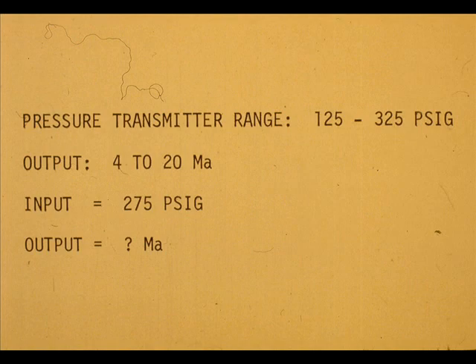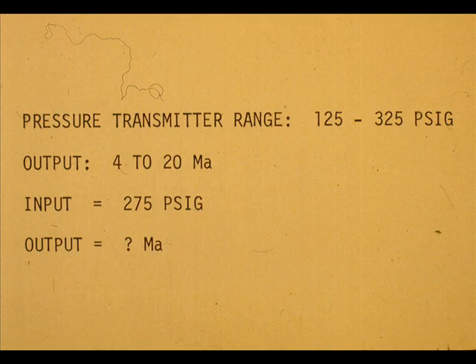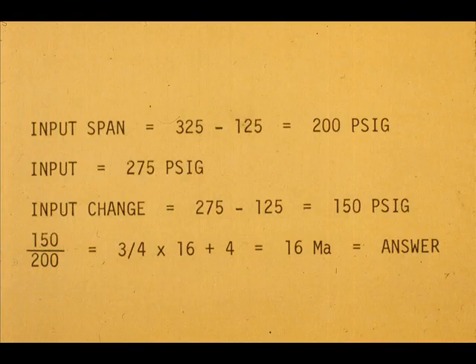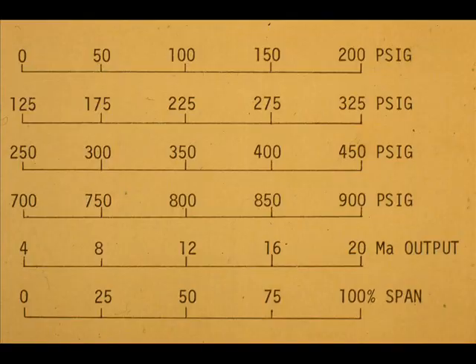Now take the same conditions and calculate the output for 275 PSIG input. 275 PSIG input is 75% of the input span, so the output is 16 milliamps. We have proved that the transmitter is concerned with percent span and not range.